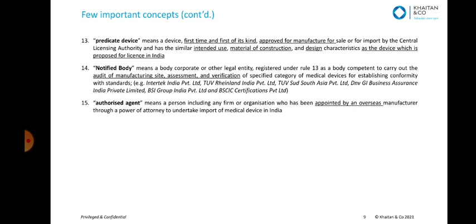What are the government bodies? There is CDSCO, the state licensing authorities, the national accreditation body, the notified body, and the medical device testing officer or medical device officer, who is the inspector. So the CLA is of course the highest body, and it takes care of the highest risk devices, which are class C and class D. Import of all devices, and clinical investigation or clinical performance related approvals, all have to be approved by the CLA, along with the coordination function of the state licensing authorities.